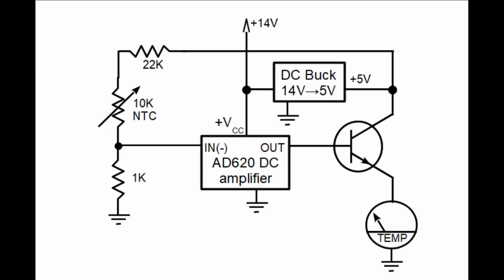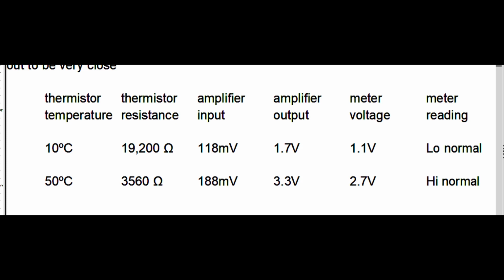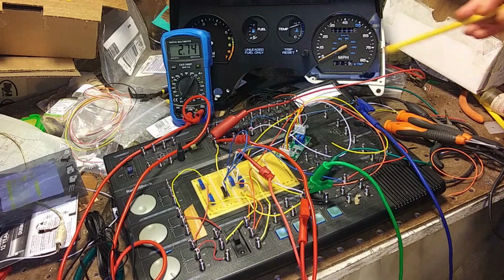We'll use the 5-volt supply we already installed for the fuel gauge as the source for the voltage divider. That will give a 118 millivolt amplifier input at 10 degrees and 188 millivolts at 50 degrees. So I just need to adjust the amplifier gain and zero offset so that those inputs result in the appropriate output voltage to give the meter readings we want, namely the upper and lower limits of the normal range on the gauge.